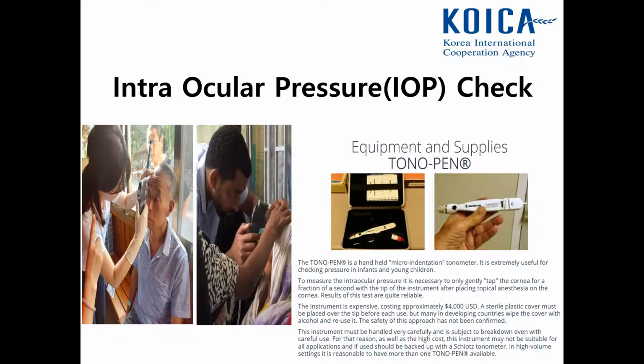Automatic tonometer needs a table and the manual tonometer needs a bed to lie on. But portable IOP equipment like Icare or Tonopen does not need a table or bed. So it is very useful for patients with poor systemic condition who can hardly sit, lie, or move. It is very light to carry and easy to check in a brief time, although these are expensive too.